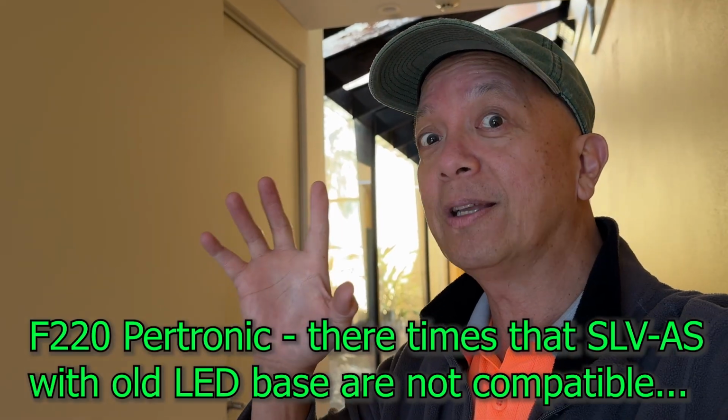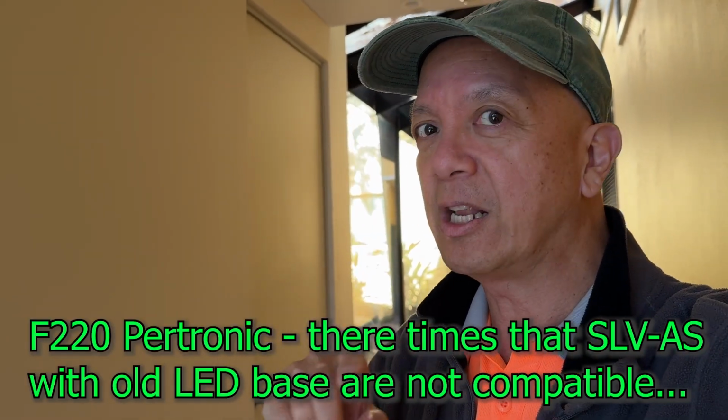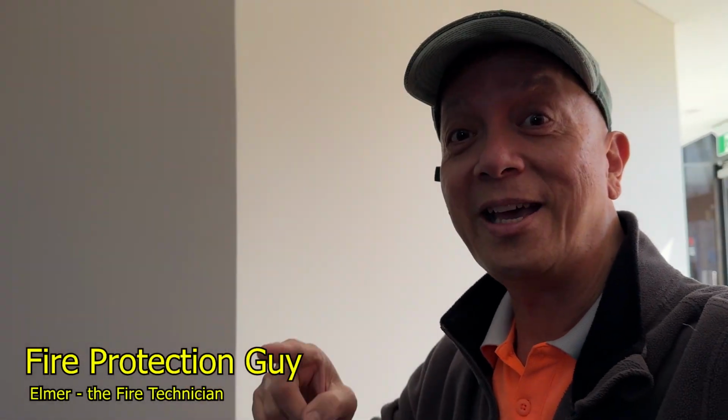Sometimes when you spray it and it goes on alarm, it is not an alarm but a fault. I noticed that in some SLV-AS. There's one zone here where I replaced the whole circuit with 2151 System Sensor because the existing SLV-AS, every time I activated it, created a fault, not an alarm.